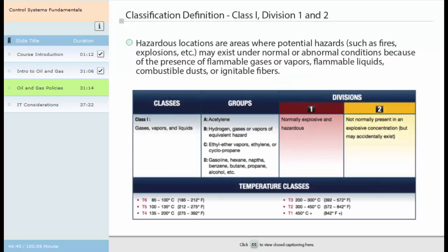Many of the standards and regulations developed by regulatory agencies focus on controlling conditions in a hazardous location. A hazardous location is characterized by its potential danger, such as frequent fires or explosions. Depending on the characteristics of the location, such as the presence of flammable gas, liquid, or combustible dust or fiber, potential danger may be a normal or abnormal condition.